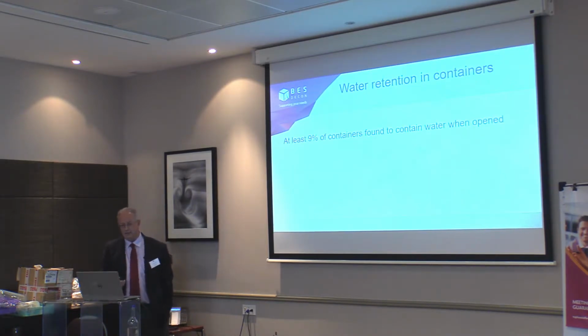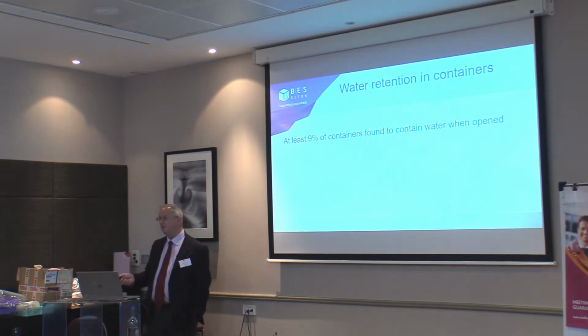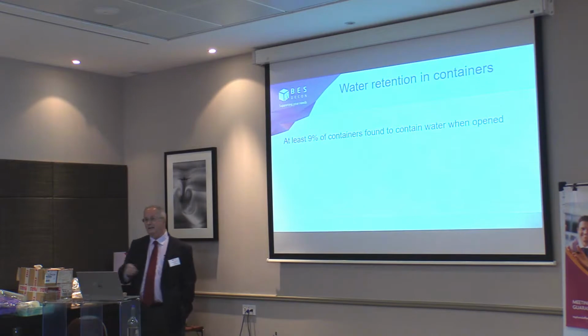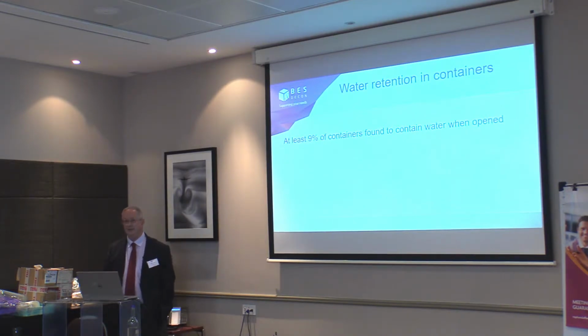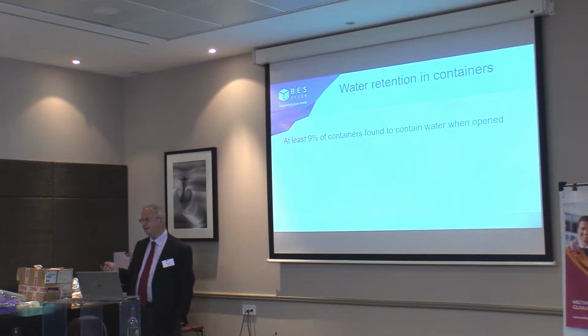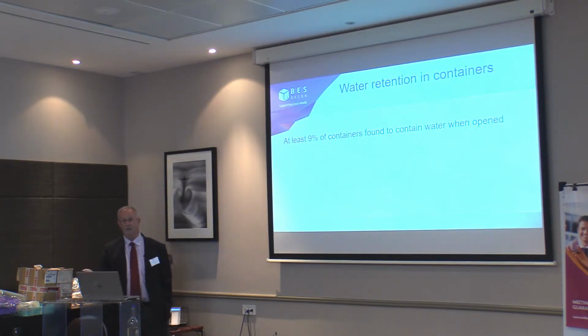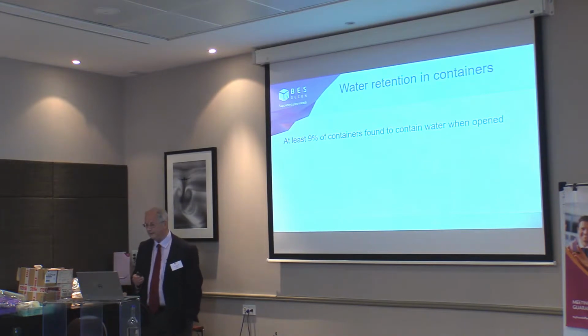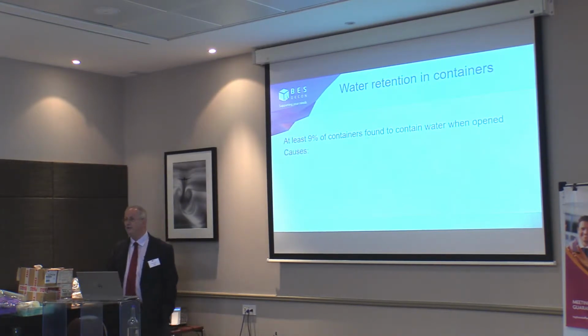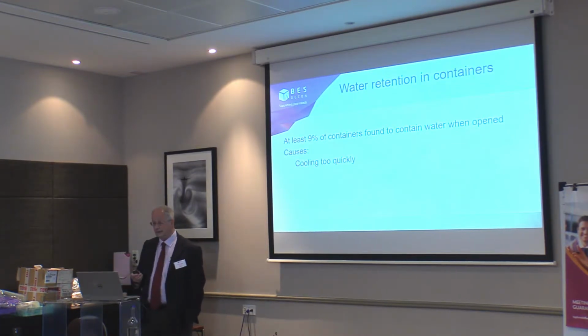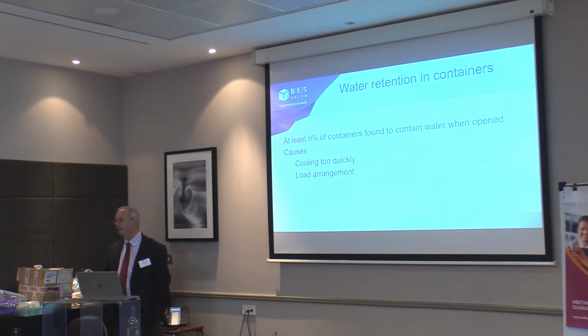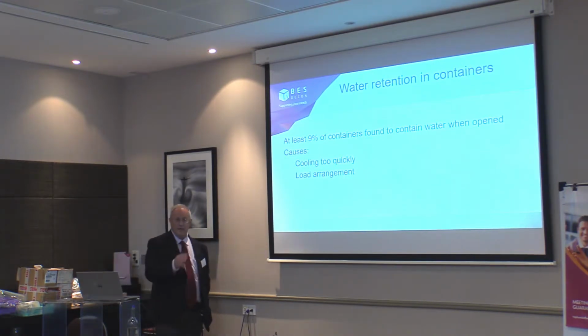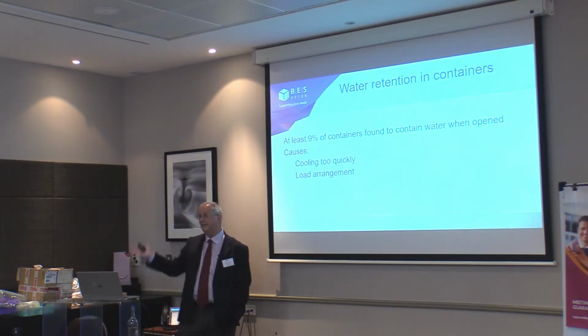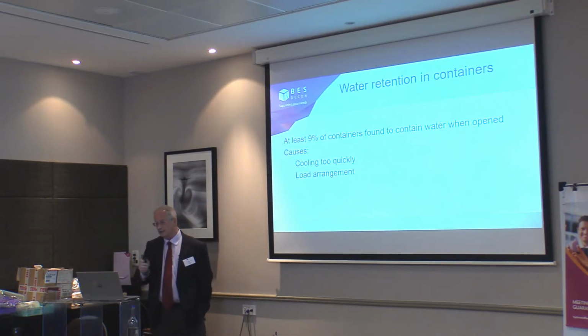One report showed that at least 9% of containers were found to contain some water when they were opened. That obviously has to lead to a cancelled operation. That's not good news, because if there's any moisture there and one or two bacteria were left, they could have started to grow. The causes of water being left inside containers often come from cooling too quickly in the sterilizer, sometimes from the load arrangement, where the load has got in the way of the vacuum and the steam getting everywhere it should be at the right temperature. So that was just one report.